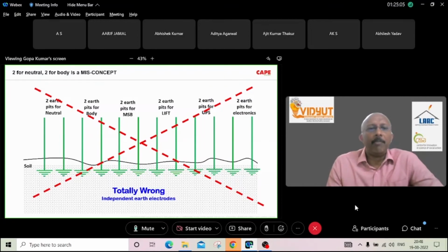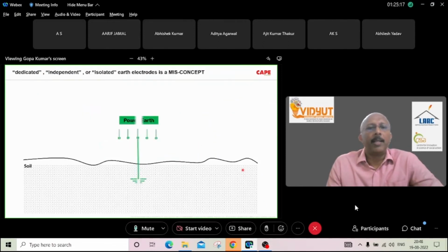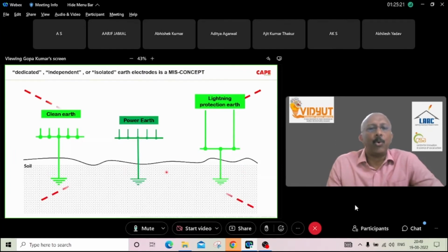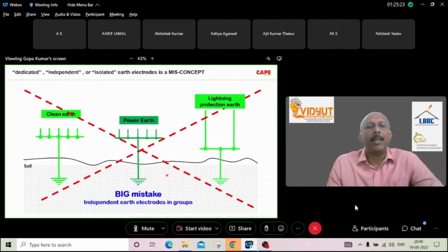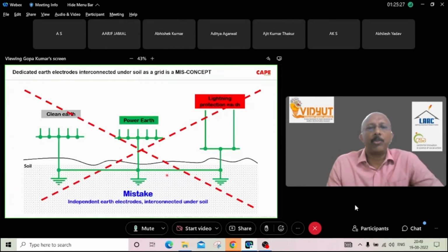the first enemy of electrical safety is this concept: 2 for neutral, 2 for body. Please understand that this never existed in our system. This was never written in any document. This kind of another way of doing earthing, so many earth pits, clean earth, power earth, lightning protection separate, these are wrong. This is also wrong.